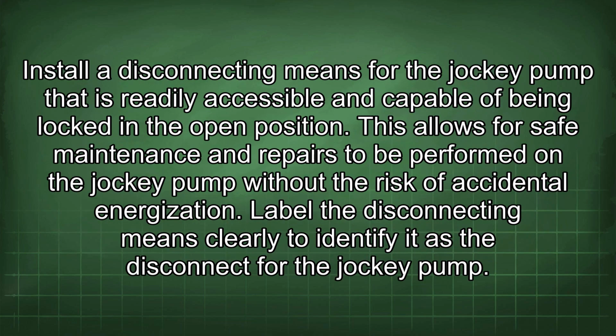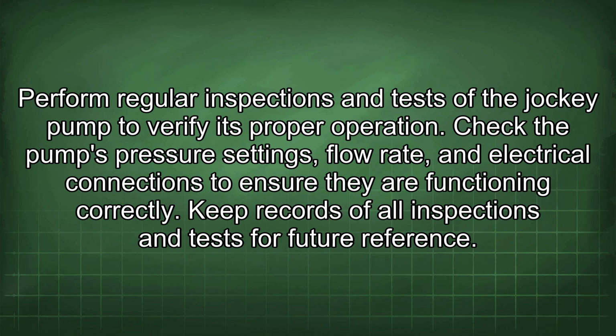shock. Install a disconnecting means for the jockey pump that is readily accessible and capable of being locked in the open position. This allows for safe maintenance and repairs to be performed on the jockey pump without the risk of accidental energization. Label the disconnecting means clearly to identify it as the disconnect for the jockey pump. Perform regular inspections and tests of the jockey pump to verify its proper operation. Check the pump's pressure settings, flow rate, and electrical connections to ensure they are functioning correctly. Keep records of all inspections and tests for future reference.